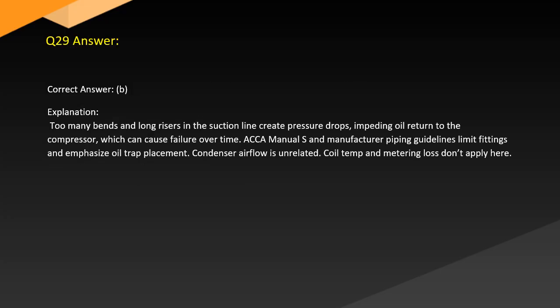Answer. Correct answer, B. Explanation. Too many bends and long risers in the suction line create pressure drops impeding oil return to the compressor, which can cause failure over time. The ACCA Manual S and manufacturer piping guidelines limit fittings and emphasize oil trap placement. Condenser airflow is unrelated. Coil temp and metering loss don't apply here.